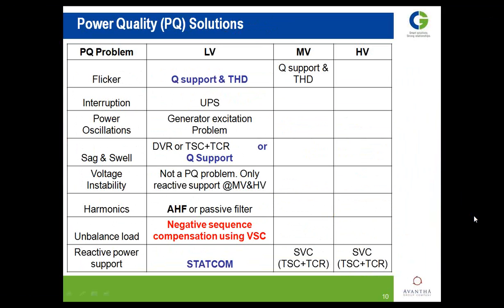To talk about medium voltage, where our concern is power quality for utilities, that comes more towards Q support, less THD, I would say, but nowadays due to all these problems and this intense non-linear load, THD is increasing, and that is getting reflected as per the transformer ratio to 11 kV, 33 kV and onwards, and that has a big impact. And SVC and thyristor control and capacitor and reactor, what we call APFCs and all that are there. And if it is high voltage or extra high voltage, basically it is SVC.